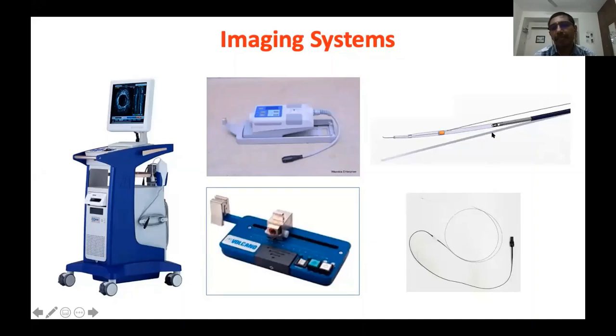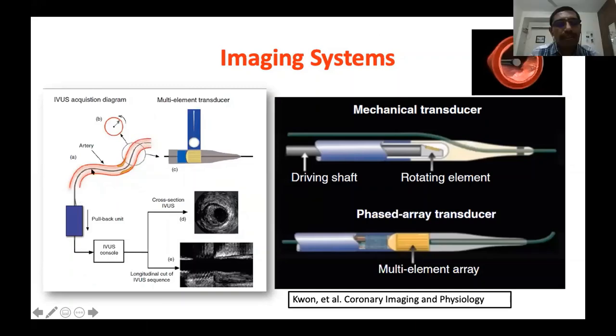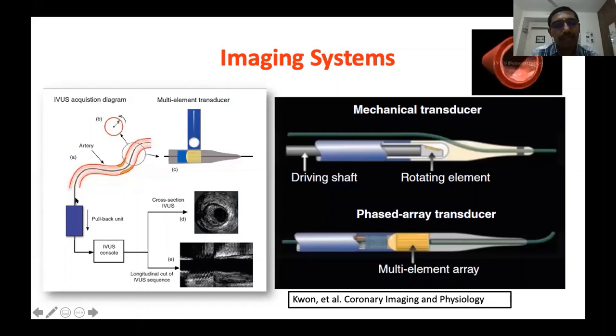The third part is your IVUS catheter. The IVUS catheter has a small transducer mounted at its tip, which is responsible for image production. The basic principle is not different from any ultrasound imaging modality such as echocardiography. The console provides electrical energy delivered to the imaging catheter and the transducer's piezoelectric crystals. These crystals produce ultrasound waves which get reflected from tissue interfaces, and a part is collected by the transducer, converting back into electrical signals. The IVUS console decodes these into tomographic cross-sectional images.